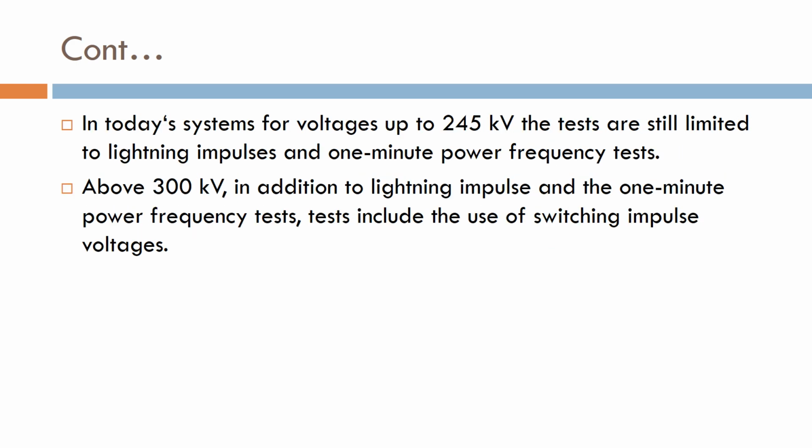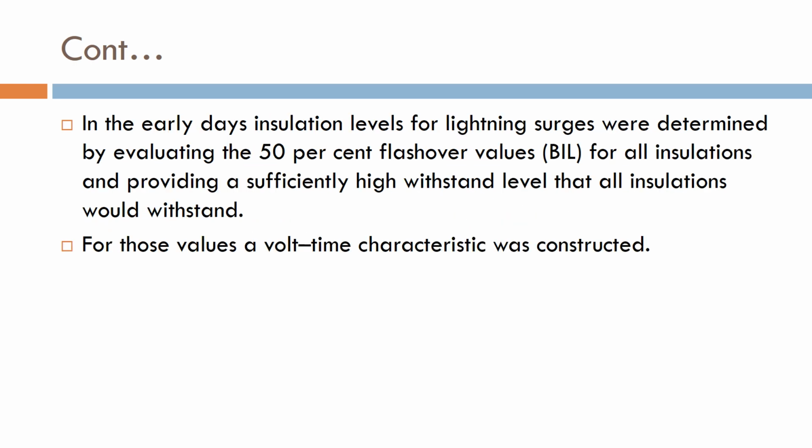In today's systems, for voltages up to 245 kilovolt, the tests are still limited to lightning impulse and 1 minute power frequency test. Above 300 kilovolt, in addition to lightning impulse and 1 minute power frequency test, the tests include the use of switching impulse voltage.